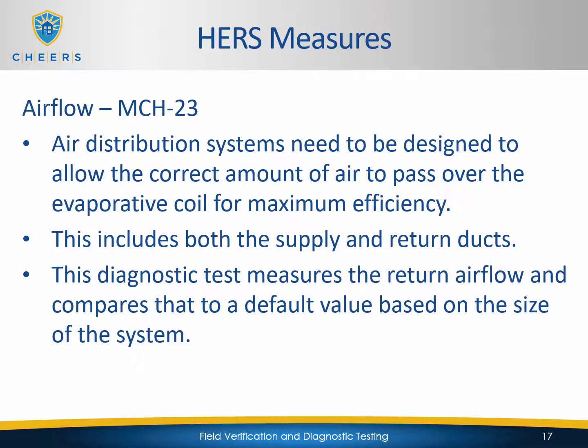Airflow is on the MCH-23. And airflow does go kind of hand in hand with the fan efficacy or fan watt draw test. So air distribution systems need to be designed to allow the correct amount of air to pass over the evaporative coil for maximum efficiency. This includes both the supply and the return ducts.